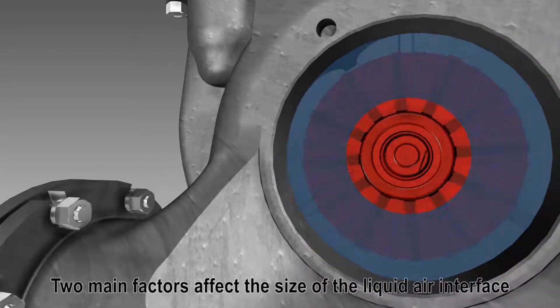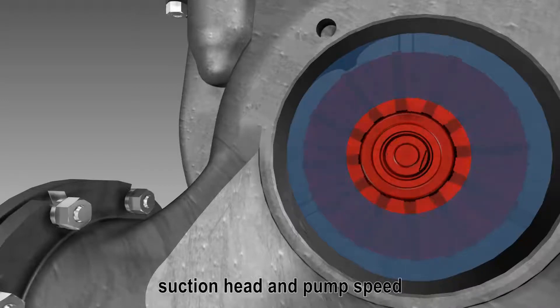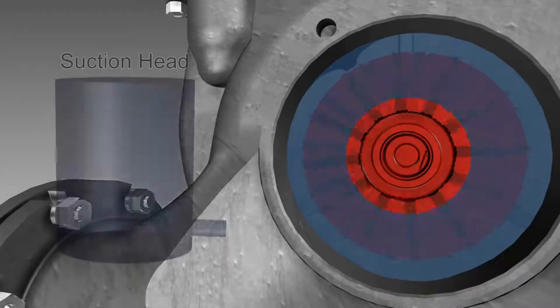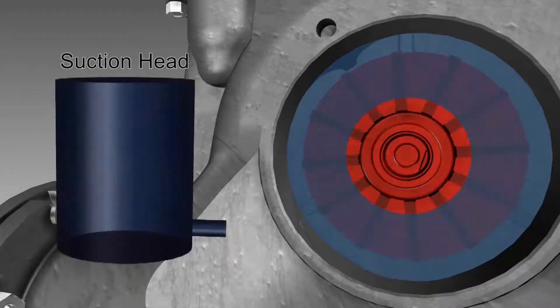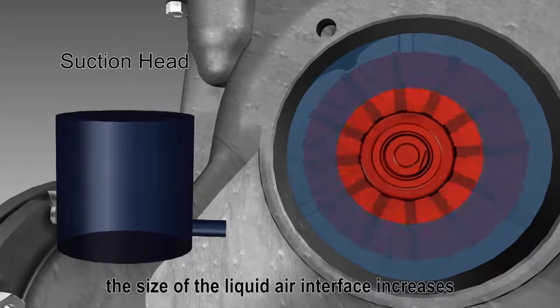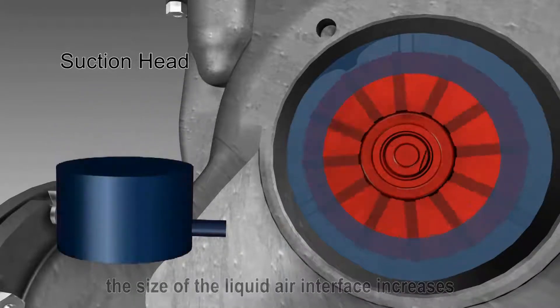Two main factors affect the size of the liquid-air interface: suction head and pump speed. As the suction head decreases, the size of the liquid-air interface increases.